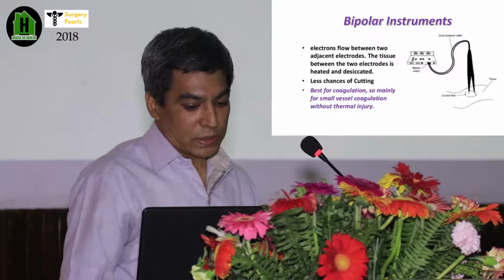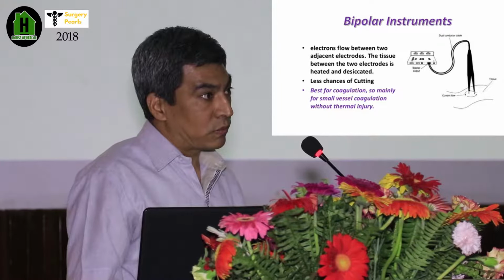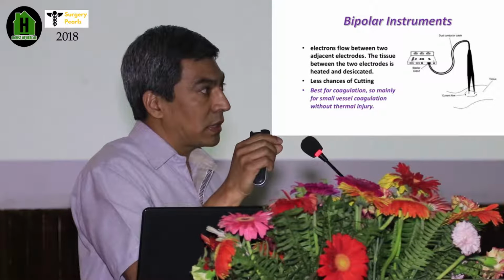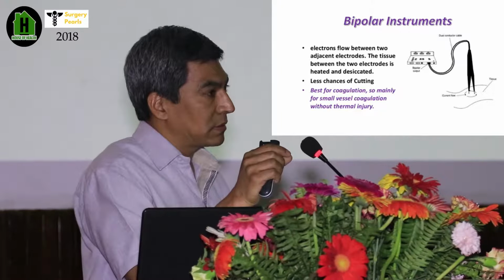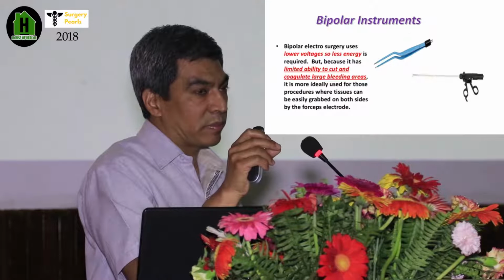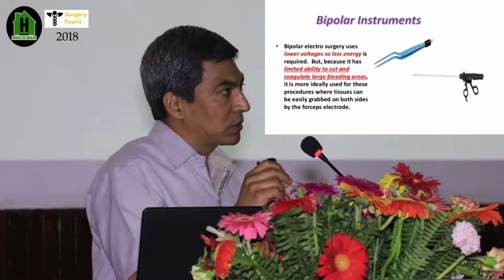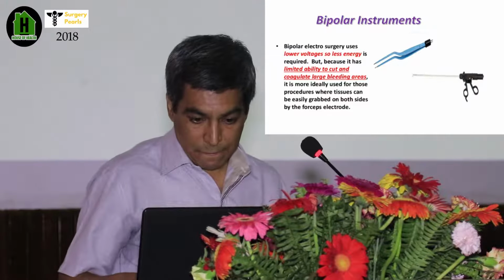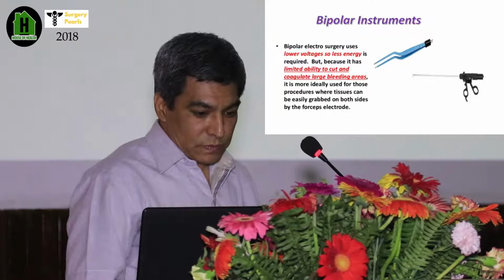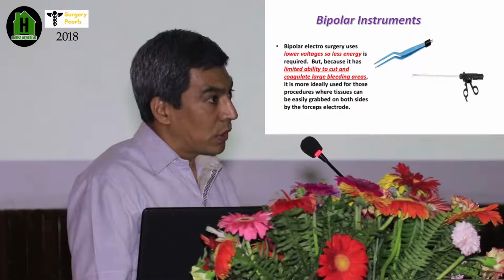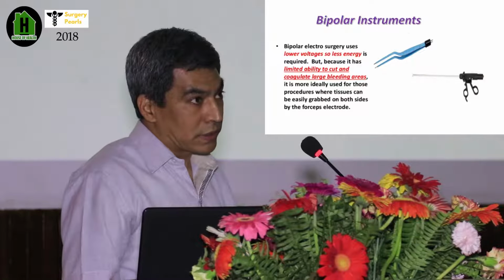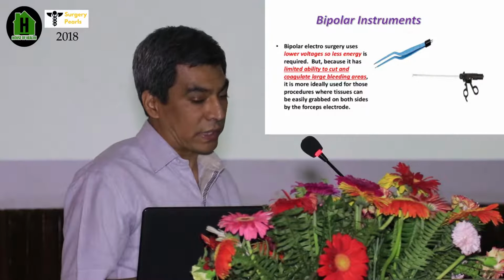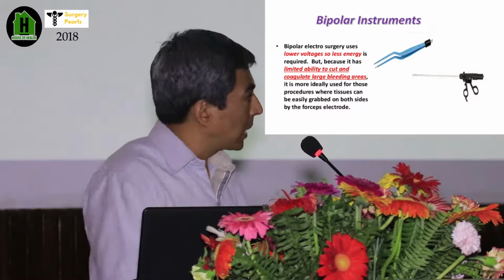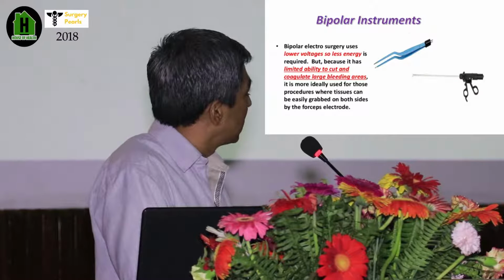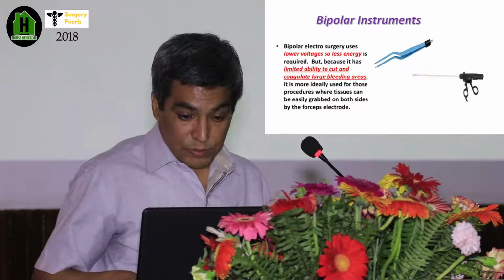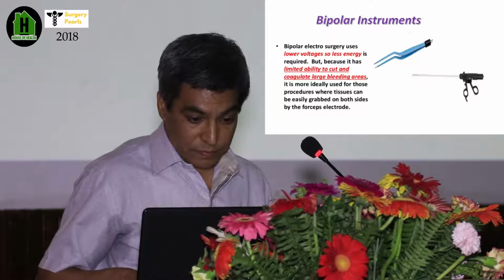This is not good for cutting purposes. It is good for coagulation purposes. And it is best for coagulation of small vessels, where you can get the vessels easily from both sides. If you can grab the vessels by both ends, this is a good device to use. It gives low voltage, so low energy. It can give only the coagulation effect, perfectly. This is the bipolar. You can use it even in laparoscopic and open surgical fields.